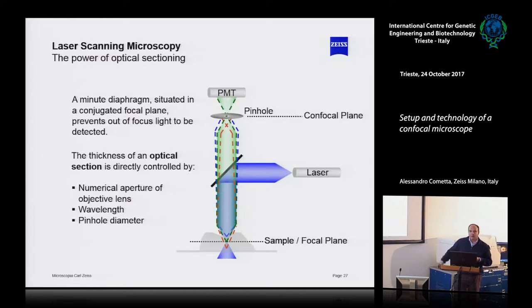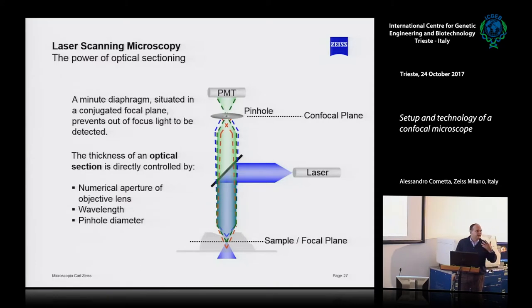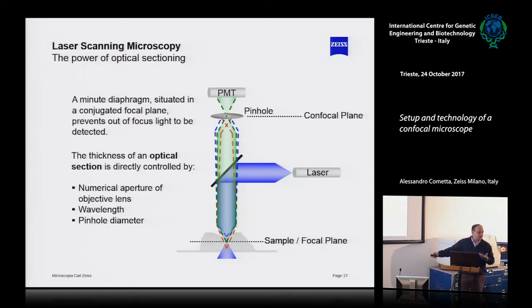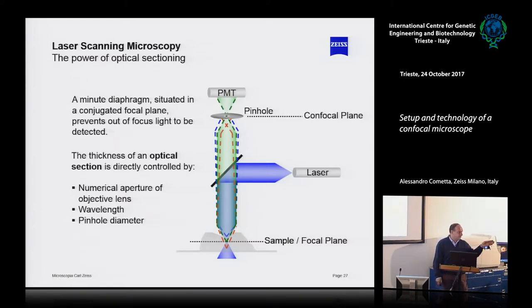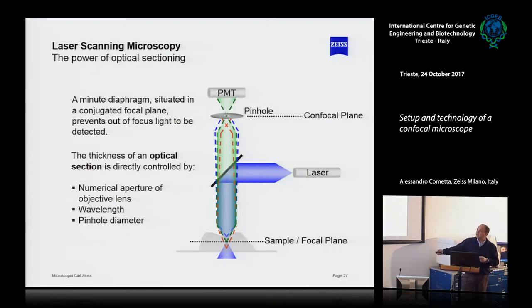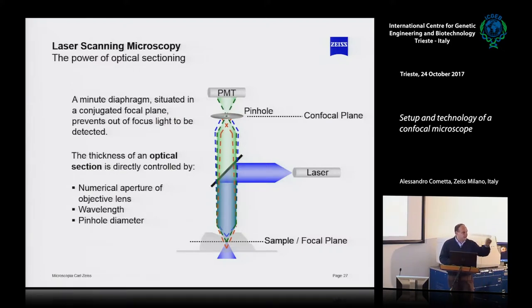This means that if I enlarge the pinhole I come back to a standard wide-field image. If I reduce the pinhole, I filter the light and remove everything that is not in focus. Coming to your question on optical sectioning — what is the thickness of the section? It depends on me: it depends on the numerical aperture, on the wavelength, and on the pinhole diameter. The numerical aperture depends on the objective, the wavelength depends on the laser source, and the pinhole diameter depends on the software slider.